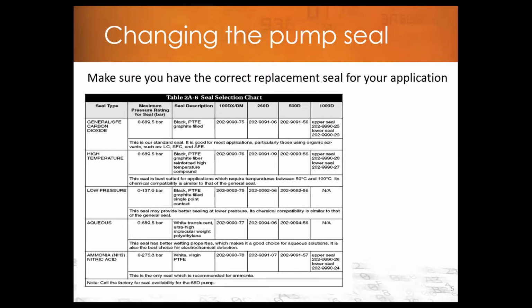And then we have a virgin or pure Teflon seal, which is the recommended seal for any customers that are pumping ammonia. So those are the seal options that we have, but the standard seal would be the graphite Teflon seal, and that's going to be good for most applications. Unless you're doing high temperature, most applications can be covered with the standard seal.